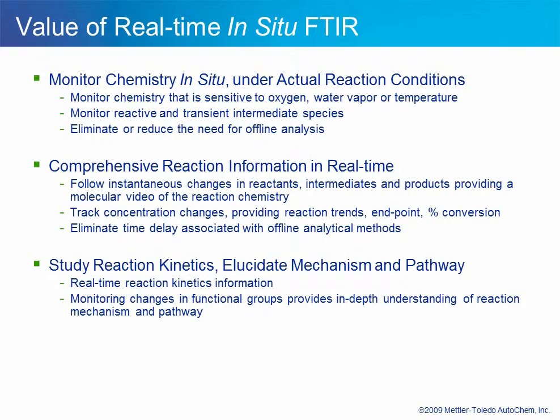React-IR is a real-time in-situ reaction analysis system. It provides the capability to monitor reactions under actual reaction conditions without having to interfere with the chemistry to get analytical information. This means that any reactions that have components sensitive to oxygen, water, or to changes in temperature can be monitored effectively, eliminating problems with taking and working up samples for offline analysis. Spectra are collected automatically as a function of time, typically every one or two minutes, but can be collected as fast as every second. This results in an extremely comprehensive set of concentration information for all key components, allowing accurate reaction initiation and endpoint determination, as well as detection of transient reactive intermediate species. In academia, this information is commonly used to understand reaction kinetics and to elucidate mechanism and pathway.